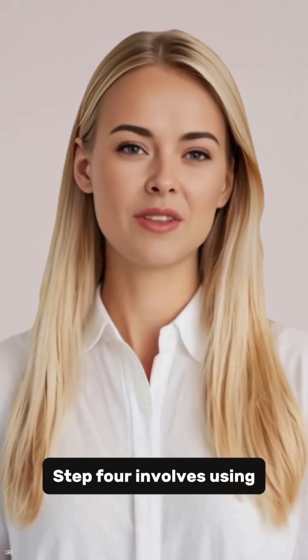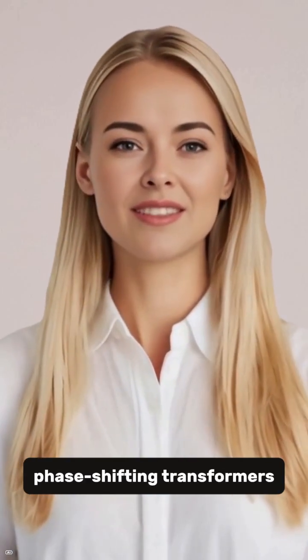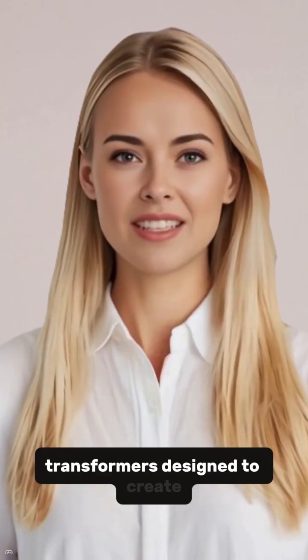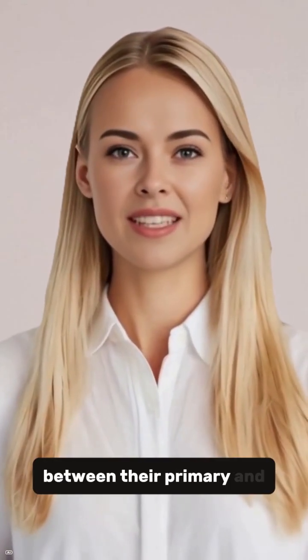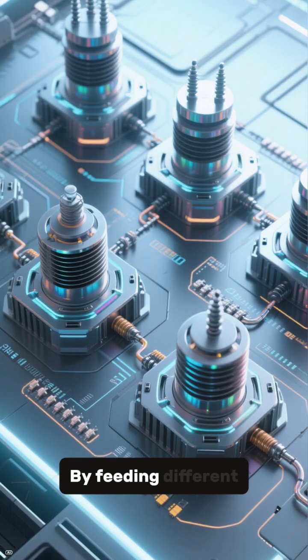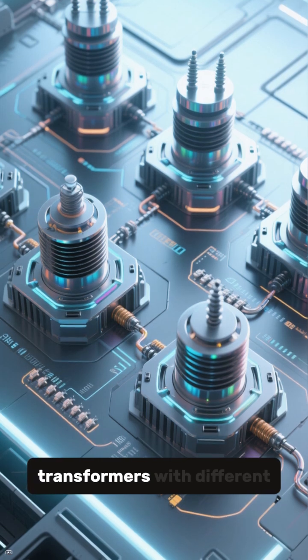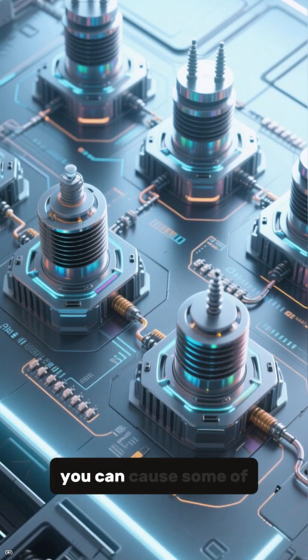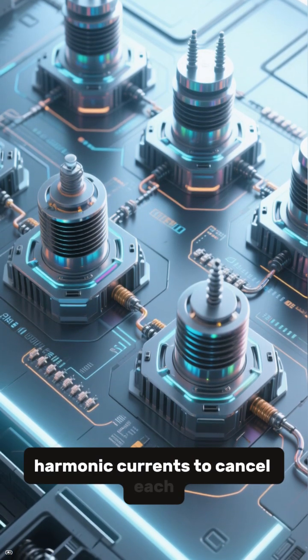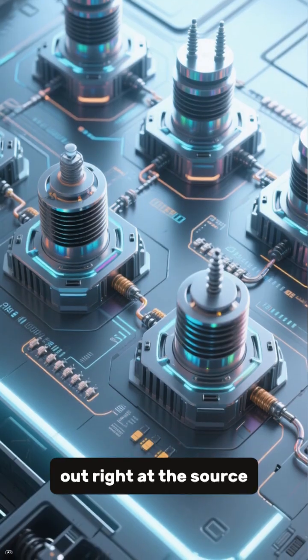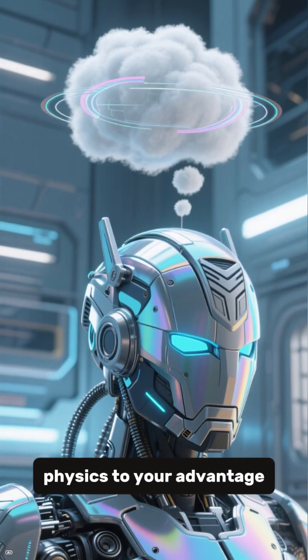Step 4 involves using phase-shifting transformers. These are special transformers designed to create a phase shift between their primary and secondary windings. By feeding different nonlinear loads from transformers with different phase shifts, you can cause some of the harmonic currents to cancel each other out right at the source. It's a clever way to use physics to your advantage.